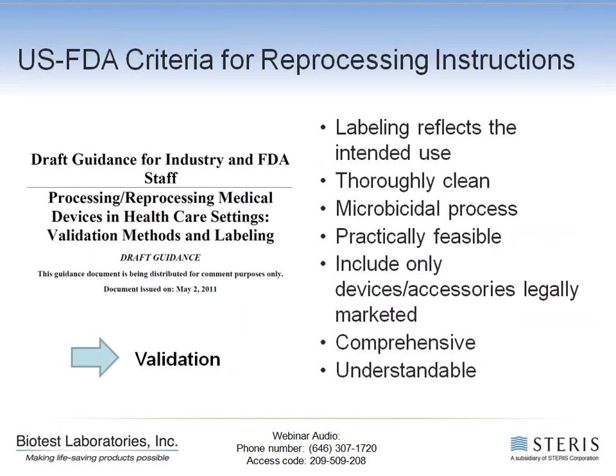A good way to approach processing from the start is by risk analysis. Risk analysis and management is critical to ensure patient and clinical staff safety. It is intended to be applied to all stages of the life cycle of a medical device, including risks associated with reprocessing. As part of the risk analysis activities, the design and use of the device should be considered both from the point of view of the physician using the device and also the personnel reprocessing the device. Risks to consider may include mechanical, electrical, chemical, or biological hazards resulting from reprocessing steps. These risks should ideally be considered early in the development of a device, rather than at the end of the development cycle.